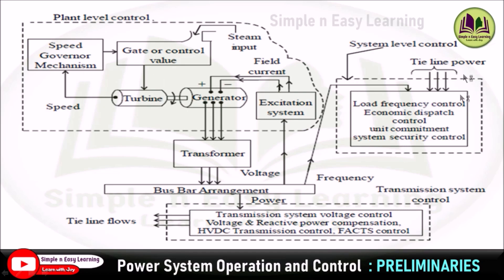Now we are going to see about the system level control. The first one is load frequency control — specifically, secondary automatic load frequency control. In the secondary ALFC control, the frequency sensor senses the frequency of the bus bar and this frequency is compared with the tie line power frequency in the signal mixer. The output of the signal mixer is the error signal called area control error (ACE). This area control error is sent to the speed changer through an integrator, and the speed changer gives the reference speed to the speed governor.